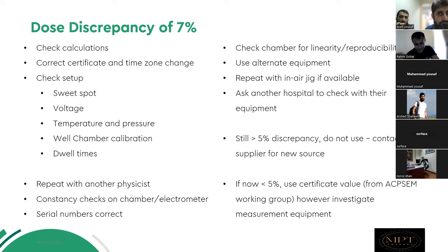No, we will put the measured value, because when we calculate and the dwell time is generated, it gives the time according to the source activity, not the certificate activity, I guess. But now you are taking care of it, right? Through the time zone difference. That's fine. The decay in the activity is taken care of. That's fine.